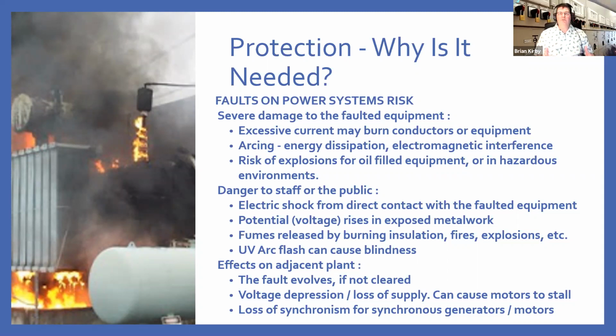And then if nothing is done to clear the fault, it may evolve, and that means it will spread across your system, damaging and affecting other parts of the network. Voltage depressions and loss of supply can happen. You can have motor stalling. Voltage depressions will cause things like wind farms to go offline, so you lose part of the generation at that point. And if you lose synchronism, you may find that part of your network isolates and becomes islands. And then you have to start doing shutdowns. And the biggest risk is ultimately you go to a full blackout and you have to do a black start again.